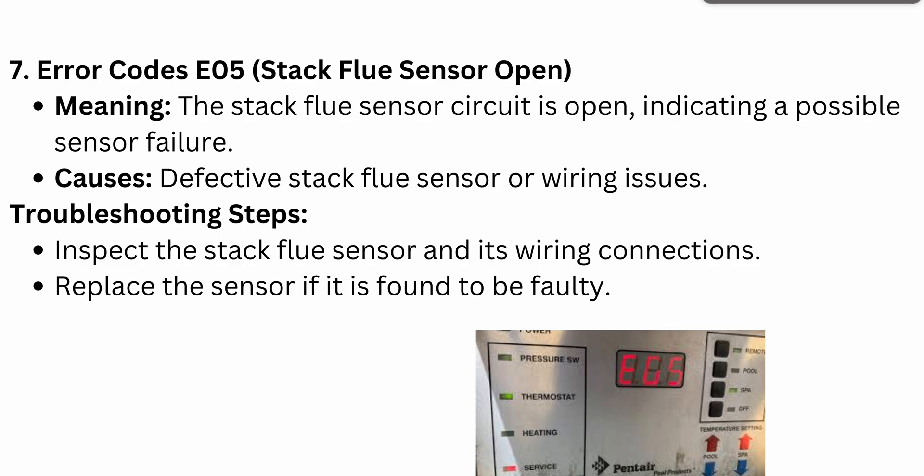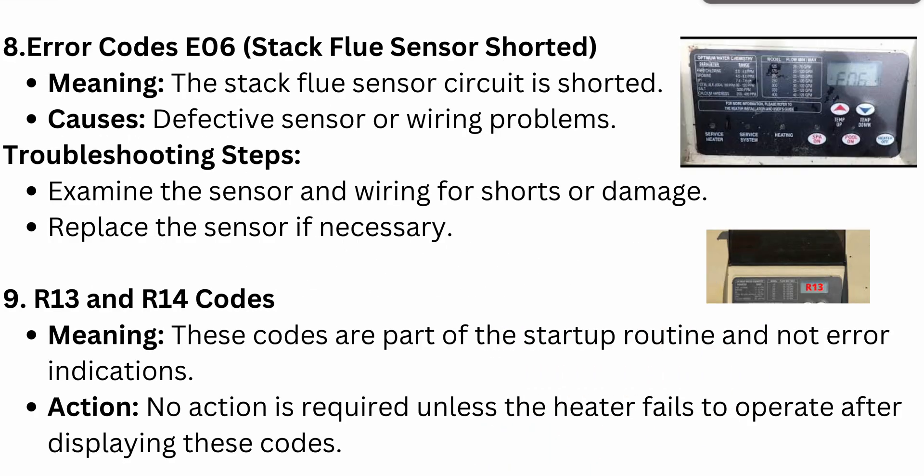Error code E06 is stack flue sensor shorted. It means the stack flue sensor circuit is shorted. The causes can be a defective sensor or wiring problems. The troubleshooting steps are to examine the sensor and wiring for shorts or damage, and replace the sensor if necessary.